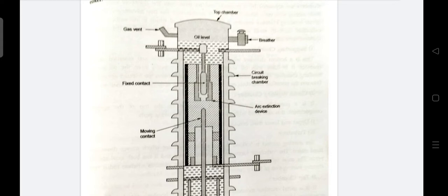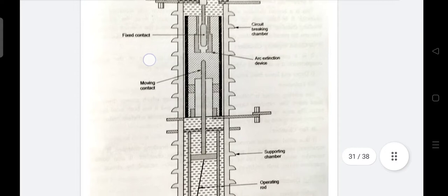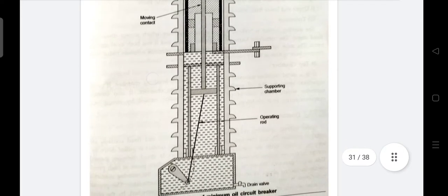A low or minimum oil circuit breaker uses a small container having oil which is just enough for arc extinction. The container of oil is supported on porcelain insulator so that required insulation can be obtained for live parts from earth. Thus low oil circuit breaker has added advantage that it requires less space than the bulk oil.